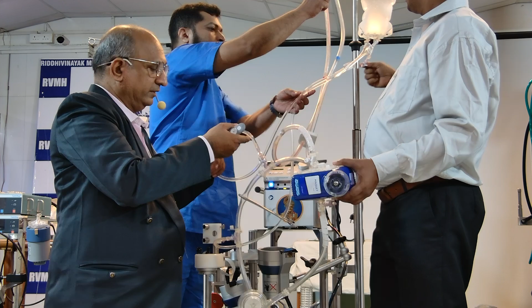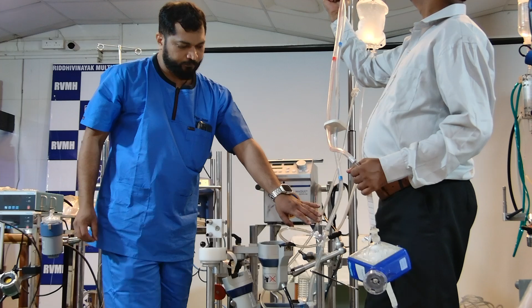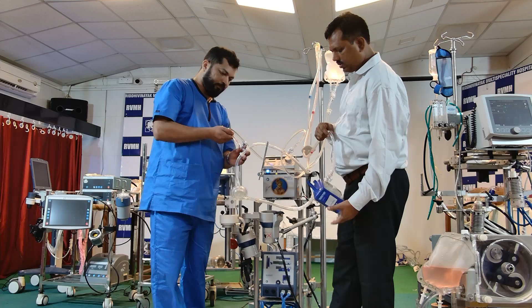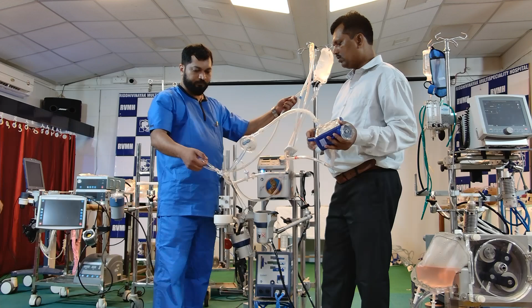Then, when it comes out of the oxygenators, both of them unite here. It's a reverse Y. One blood stream is coming from this oxygenator, one from that oxygenator, both get united here, and then it goes to the patient. This is a dual oxygenator connection and you require a double Y: one Y pre-oxygenator, and another Y post-oxygenator.